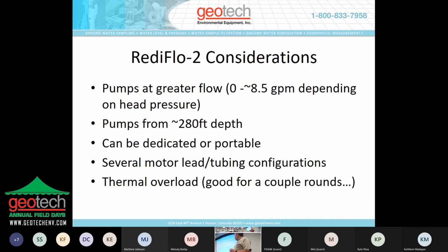This pump does have a thermal overload. Most people don't know that. They bury that in the manual. The Ready Flow 2 is very susceptible to overheating. I actually participated in the beta testing of the Ready Flow 2 when they were rolling it out in 1989 at the Grundfos factory in California. And one thing that they couldn't overcome was managing the heat that this pump will generate.